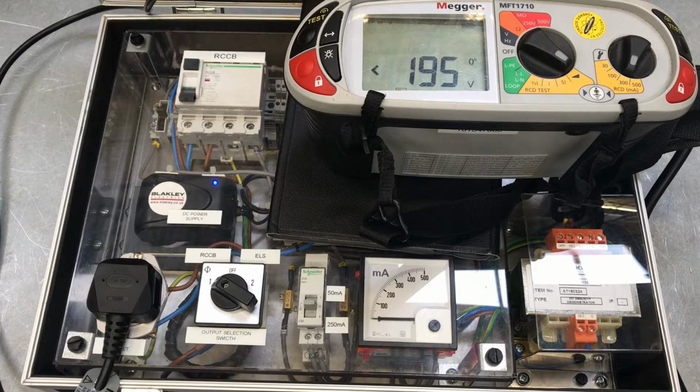Operational interruptions can give false readings, and this is the problem. I've got certificates handed to me where they've said it's great, I've gone out there, pushed the button and gone, no. It's not my contractor's fault, it's the operational restrictions of the EICR that I'm doing.